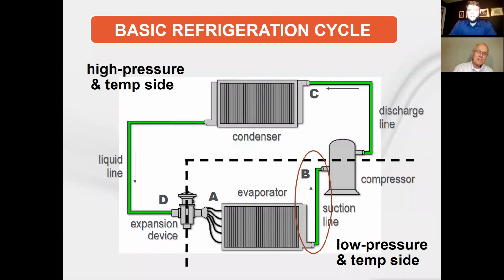Yeah, one of the biggest challenges in the split system is, when we've gone to microchannel coil and reduced the volume of refrigerant, and you add another coil into the mix, such as a hot gas reheat coil, it's very difficult to ensure that the refrigerant is balanced as it travels from either the condenser or the hot gas reheat coil, because a lot of times it might be modulating hot gas reheat, which is what most of the market is requiring right now. So in order to keep the refrigerant balanced and not starving either the compressor or the condenser, and like Mike said, ensuring that oil travels throughout all parts of the system and is not getting trapped in spots.